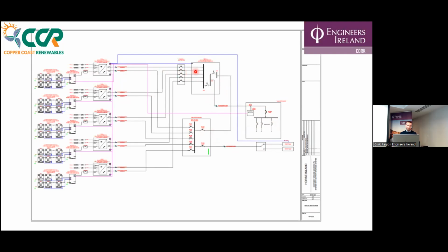The real reason it had to be done this way is that if the batteries reach 20% usage, the diesel generator kicks in. The generator can't supply straight through the inverter via the normal input, it has to come in through the EPS load. That's why we have two separate boards, so the generator can charge the batteries while also exiting here to supply the load through these changeovers, with this switch open.